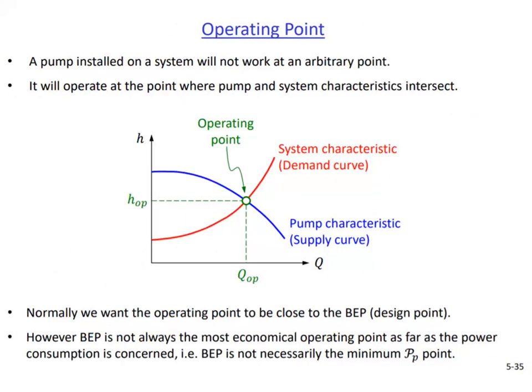After determining the system curve, its intersection with the pump's HQ curve gives the operating point of the pump. For the given system, the pump will operate at this point. We want this operating point to be close to the best efficiency point. If this is not the case, we can consider using a different pump, or we can try to make modifications in the system to shift the operating point.